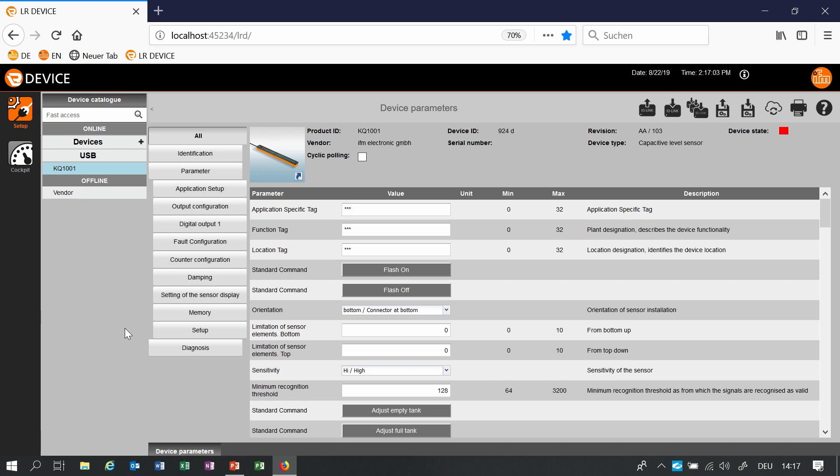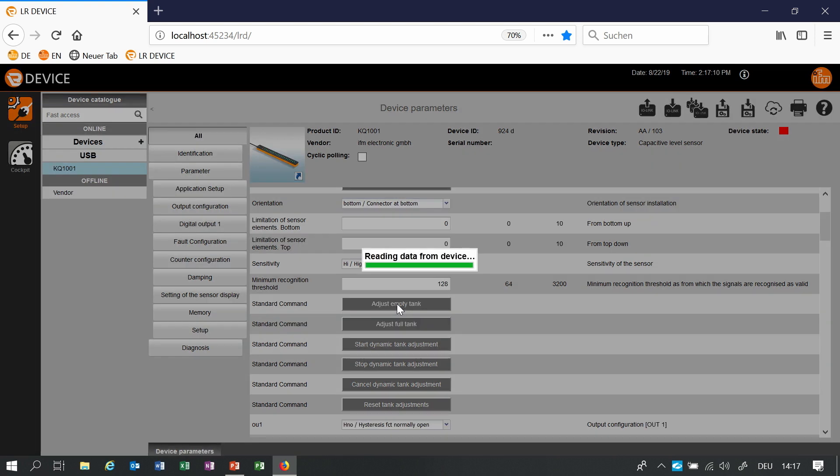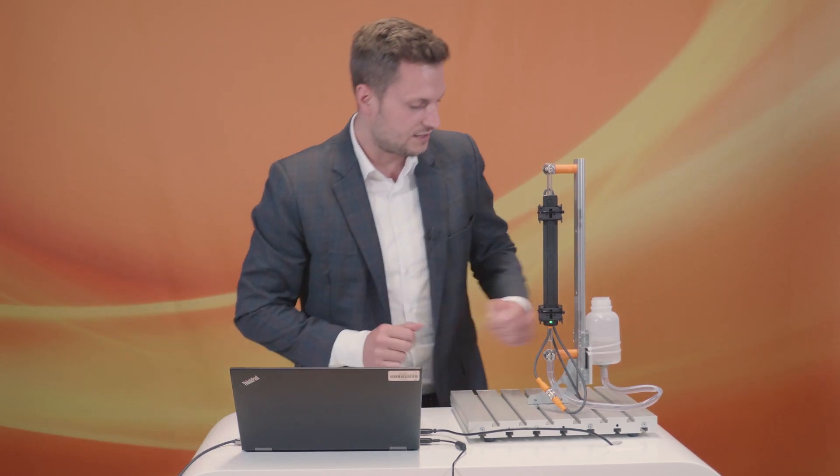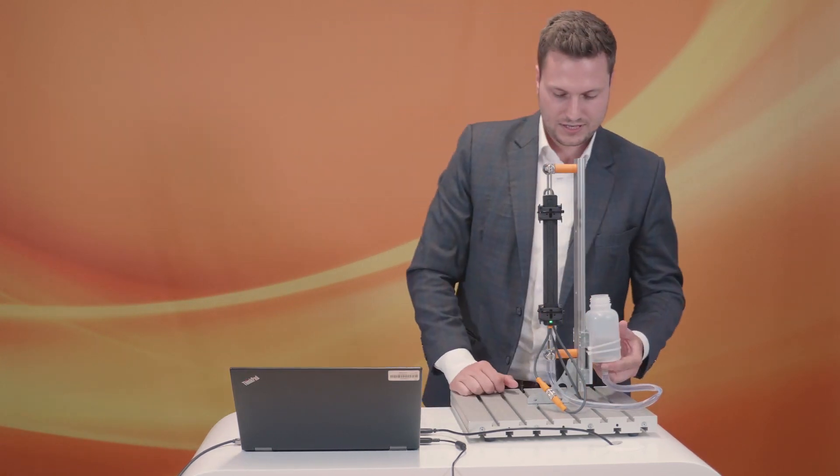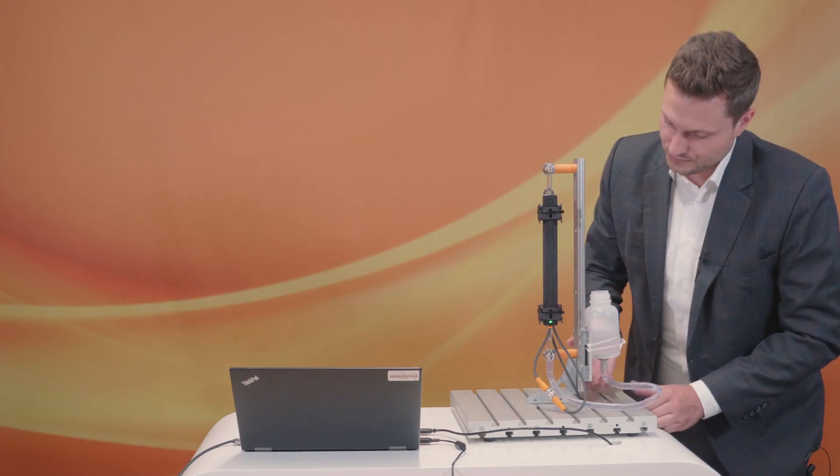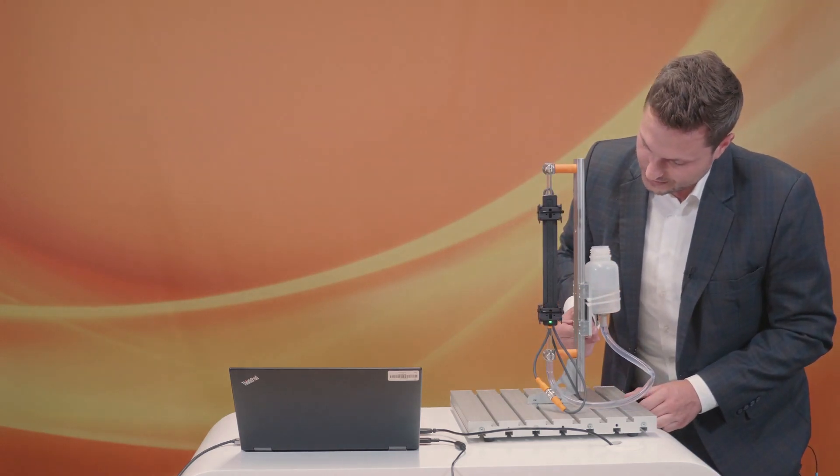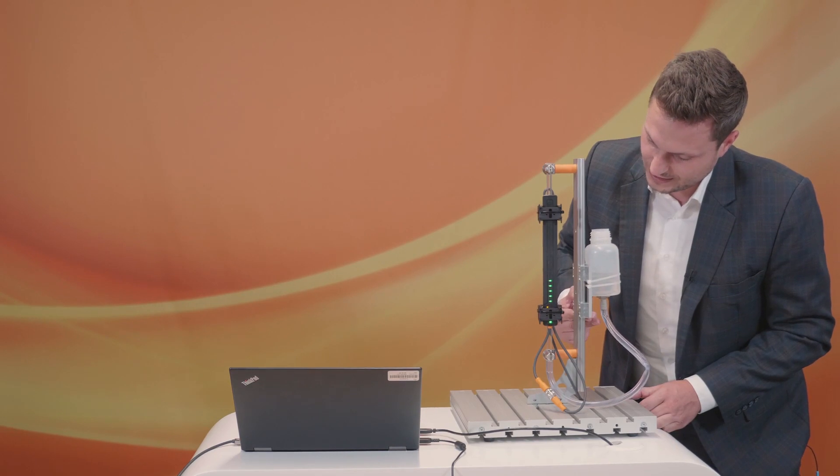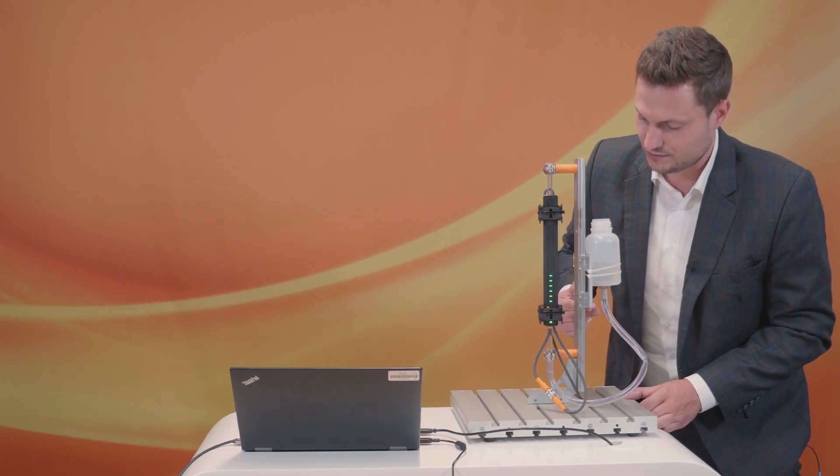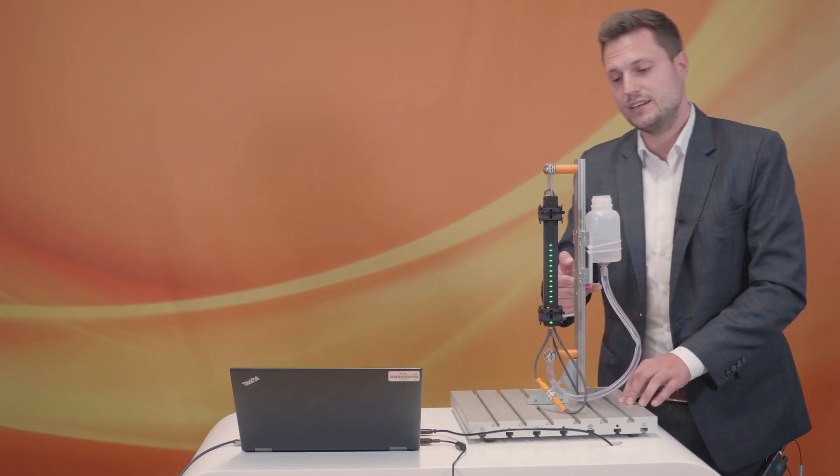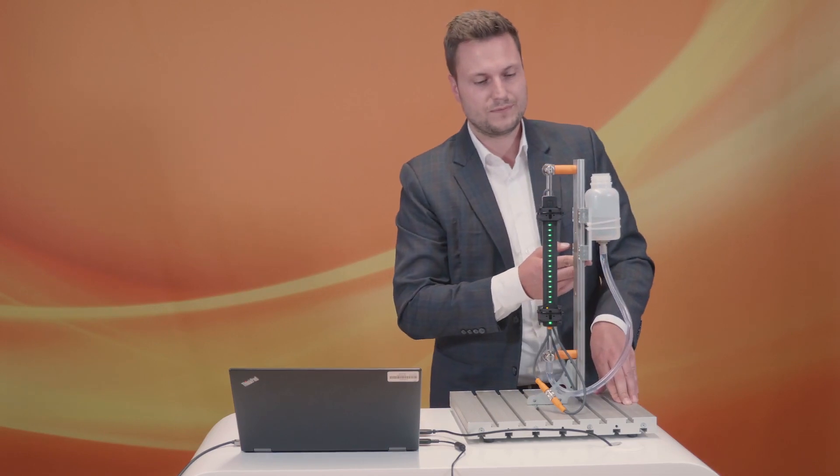For an easy setup we just have to make an empty teach something like an offset that the sensor doesn't see the tank wall anymore or in this case this small tube. It's already finished and I just have to rise the water here and we can see that the sensor is already working just with one teach.